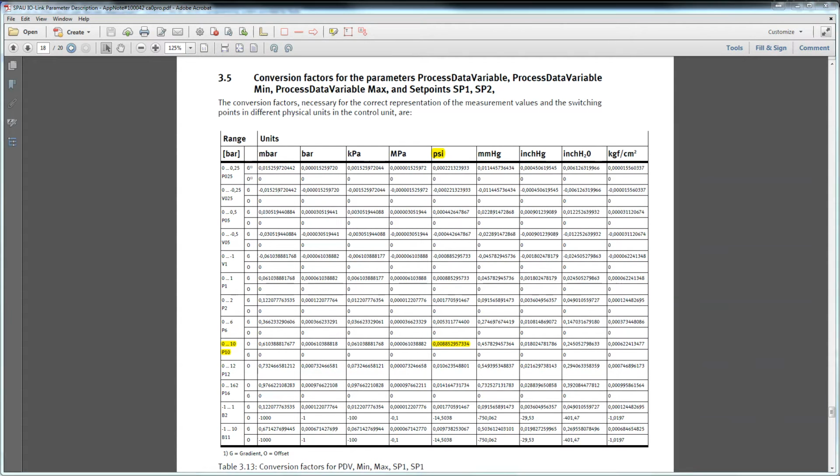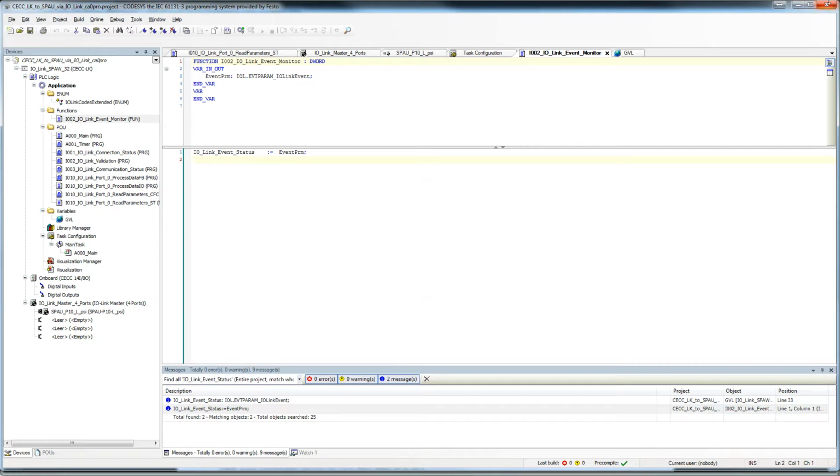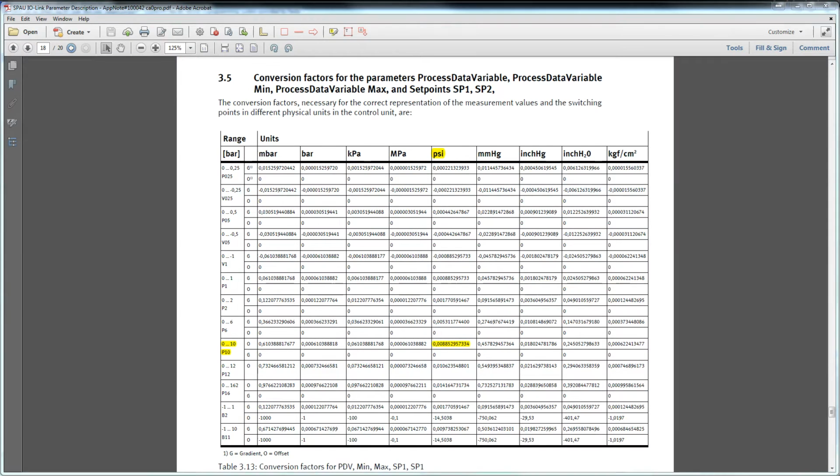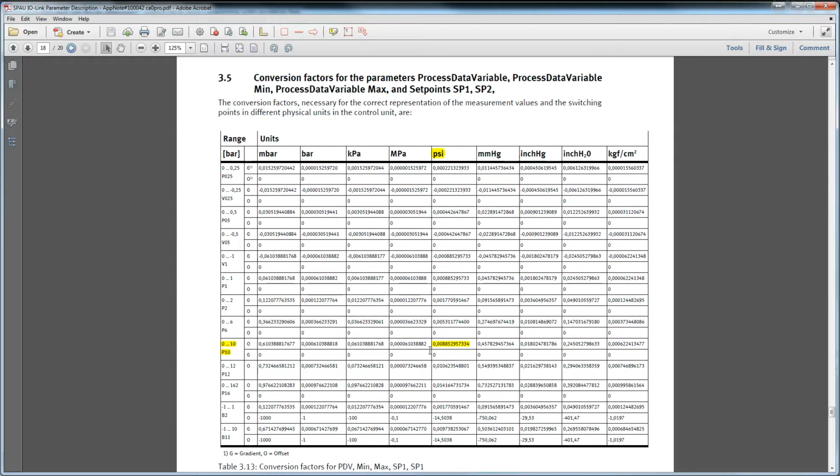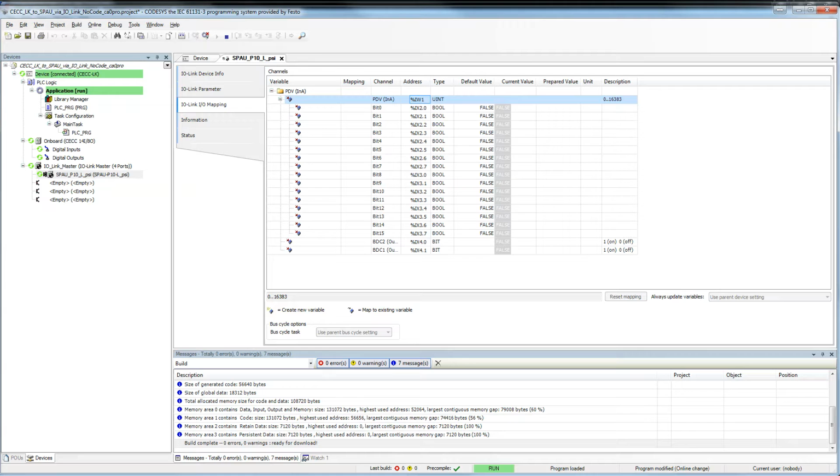So the raw data, in the project here, not this project, this one right here. So this 0 through 16383 needs to be multiplied by, in my case, because I'm using 0 to 10 PSI, and that's the switch I have here, you just correlate here. I would have to multiply that number by this value, the scaling factor, to get the correct pressure or PSI from the device.